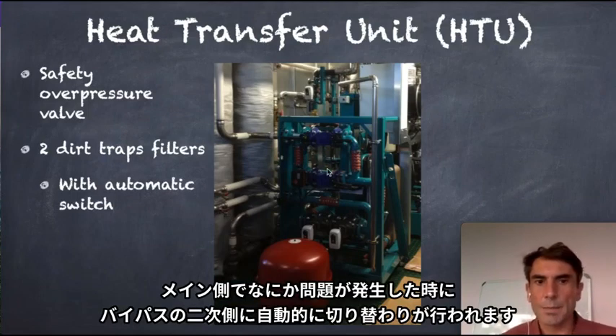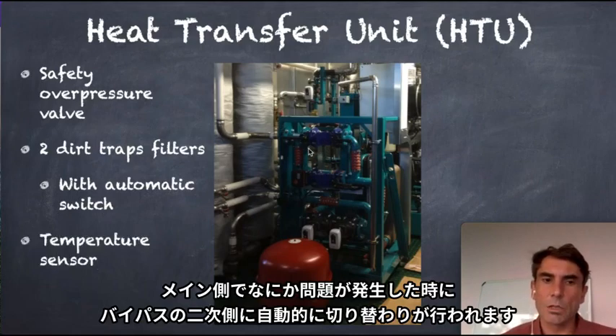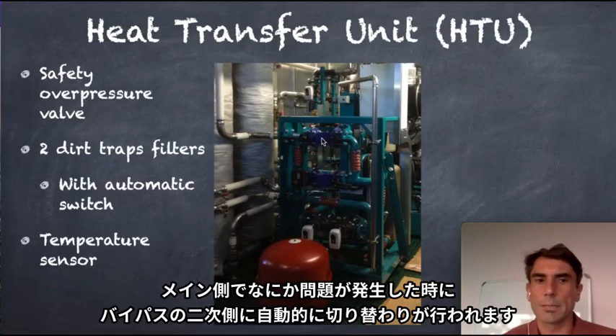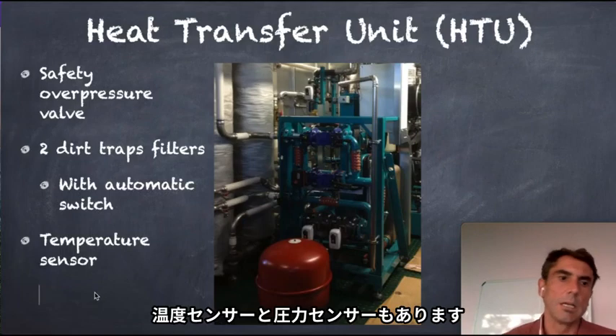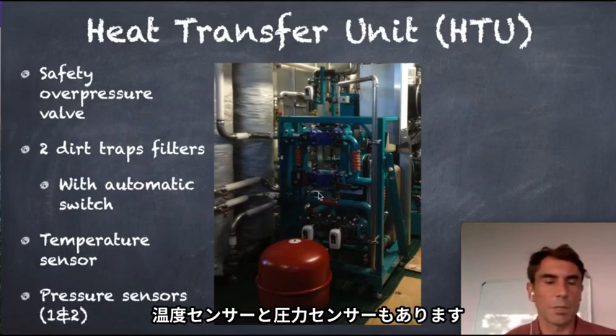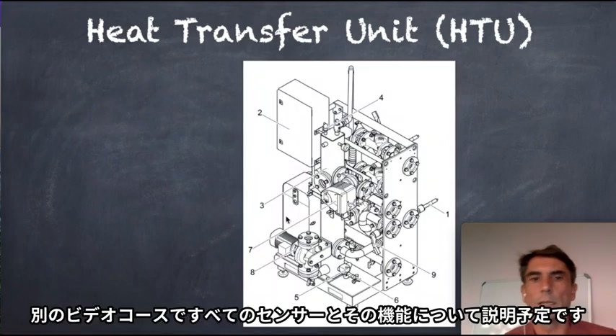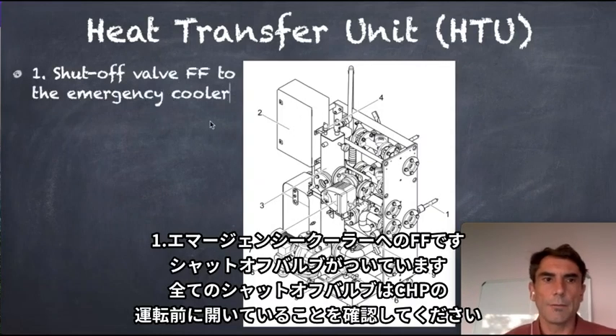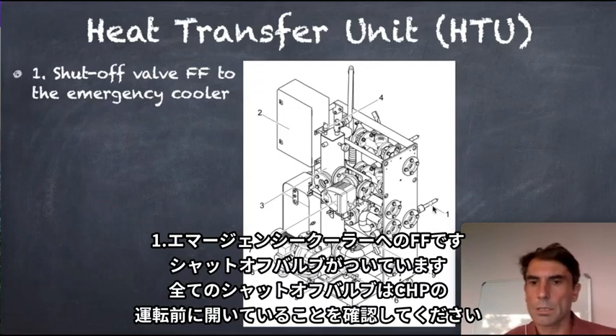So with the automatic switch, that means the control will automatically switch to the second one, the bypass one, if the first one gets some problems. We have temperature sensors and pressure sensors, as I mentioned already. We will go into the sensors in a separate video, much deeper about all sensors or functions of the CHP. Here is the emergency cooler connector, forward flow, and there is a shut-off valve. It is always important to make sure that all shut-off valves are open before you operate the CHP.